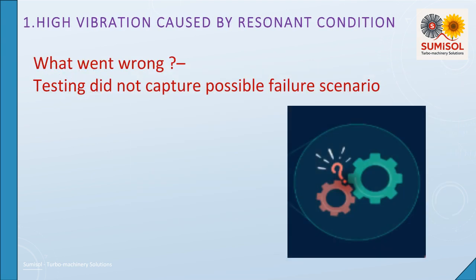The unit was supplied with a VFD-driven motor to supply flow on demand. However, due to logistic issues, the VFD-driven motor was not used. Instead, a flow control valve was used to vary suction flow conditions generated by variable speed pumping. Hence, the possible resonant condition at a particular speed band could not be captured.